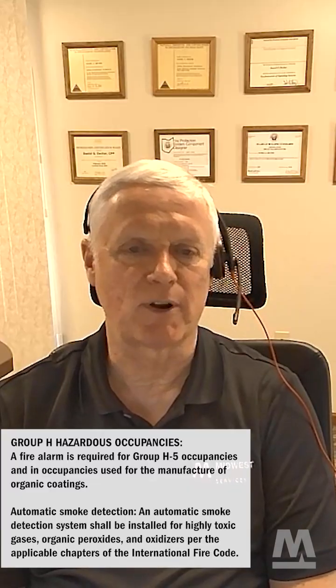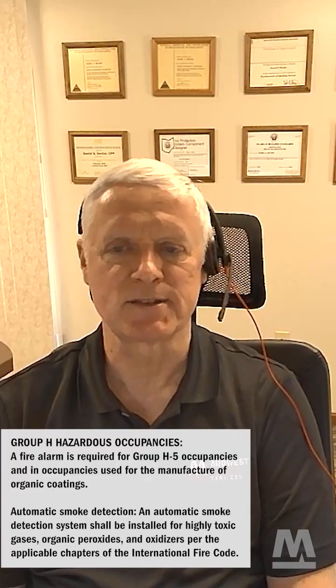The requirement is for automatic smoke detection, and it has to be installed for occupancy using highly toxic gases, organic peroxides, and oxidizers per the applicable chapters of the International Fire Code. Basically, if we're getting into a Group H occupancy, I can almost guarantee you we've got a fire protection engineer involved, and he's going to be doing not only the minimum code requirements, but other things that make sense for that particular site. So Group I is where things start getting more complex.